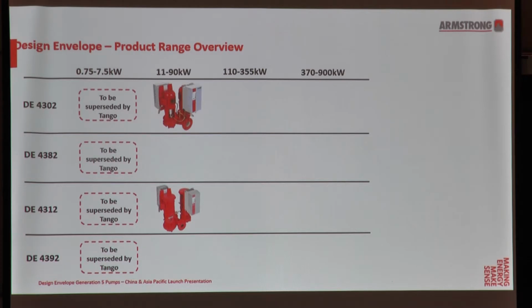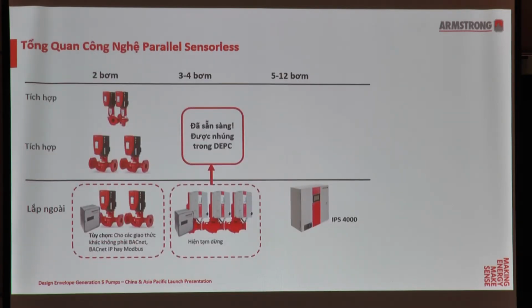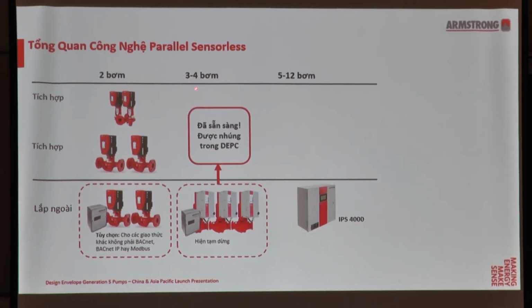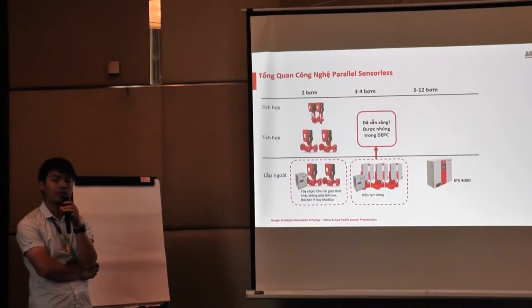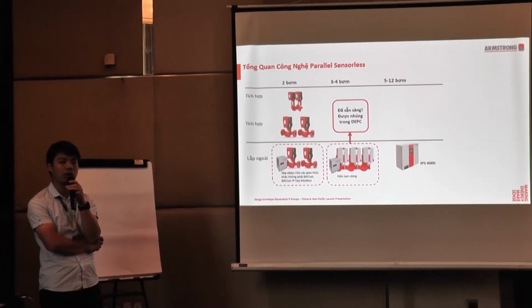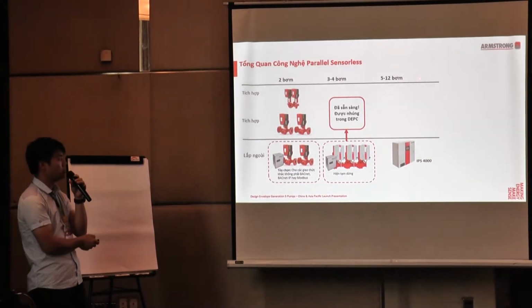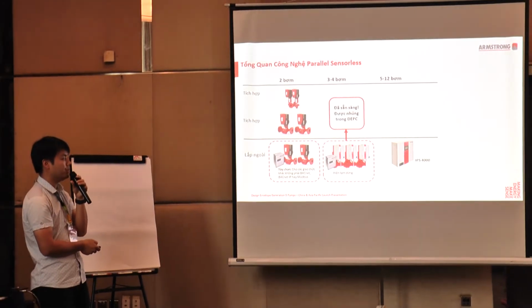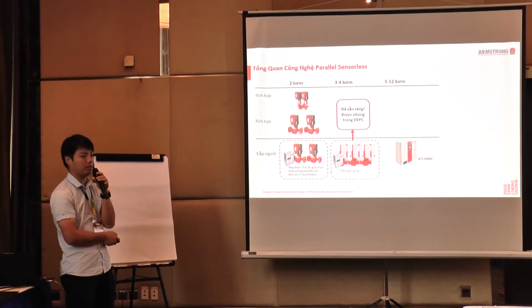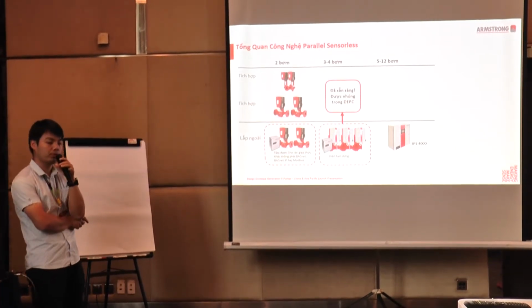Yes, we can see our twin pumps and our dual pumps. Twin means one duty and one standby. Dual pump means 2 duties. These ratings will be superseded by our Tango, and the others we'll keep the same as the previous. And for the Tango pumps, the two pumps, and also for 3 and 4 pumps in parallel, the parallel sensorless control would be embedded in our Gen 5. For 5 pumps or more in parallel, additional control panels like the IPS will be required to control the pump groups.